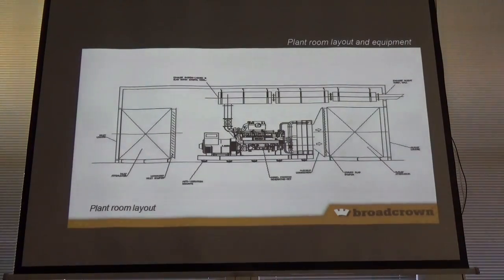You're right. Actually, the other thing to bear in mind is if this unit's going on a roof here, and your sensitive points of residential neighbourhood are here, you've got natural shielding anyway, and you've got the diagonal drop as well. I came across that on a high-rise project. We had that sort of consideration because the figures were exceptionally onerous, but again, you've got the diagonal effect and also the shielding elements to consider. So again, it's where you involve the acousticians that will really clarify these elements, what's acceptable and not, but it's getting the details so you can understand and recognise it and come to the right conclusions in context.